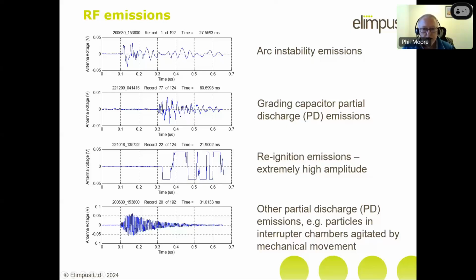The next signal, which is the second one down here, which looks very, very similar, and it's also in the low tens of megahertz, is what happens when the grading capacitor fails. And I'll have a lot to say about that in just a few moments' time. But those two are very similar, and the only way you can really tell them apart is to know whether the arc is burning. So that's why the E field is so important, because you know exactly the point where the arc goes out.